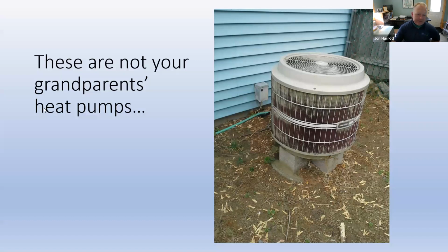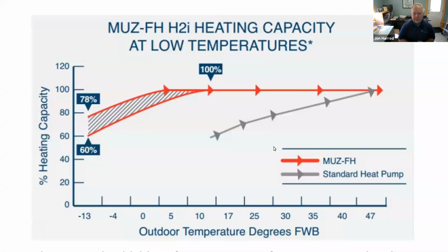The new generation of heat pumps is vastly superior. This is a performance graph for a Mitsubishi cold climate heat pump. And what it shows here in the gray is the performance curve of a standard heat pump, kind of the modern generation of the old clunker that we looked at in the last picture. And you can see as we get below 47 degrees, its heating capacity falls off dramatically. So the more heat you would need, the less the system produces. And that's part of why most heat pumps of that older generation would switch over to some kind of backup heating somewhere around 30 to 40 degrees. And below that, you'd be relying heavily on electric resistance heat or on a fossil fuel.